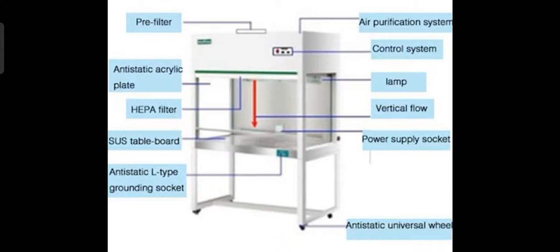There is a special filter system, that is high efficiency particulate air filters, we say HEPA filters, which can remove particles as small as 0.3 micrometer. In front of the blower, there is also a mechanism from which the air blown from the blower produces uniform air velocity along parallel flow lines.